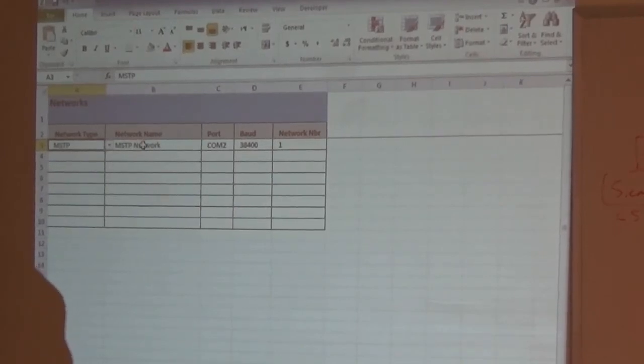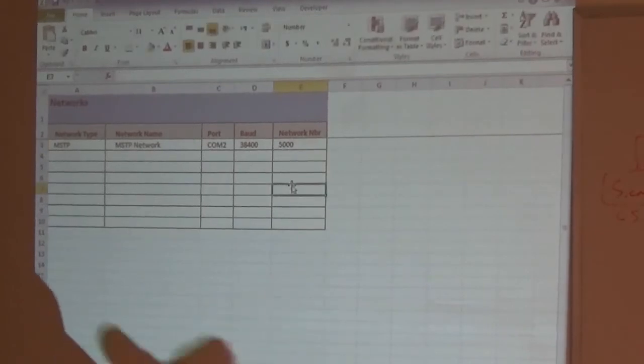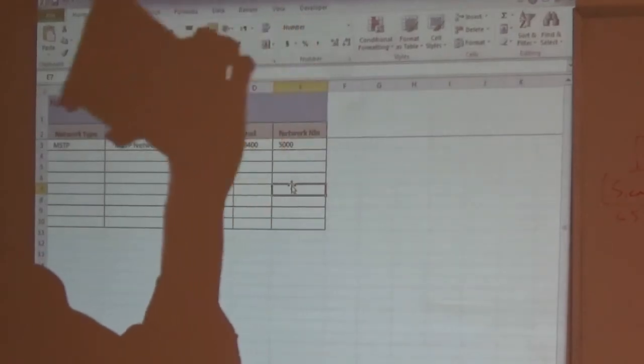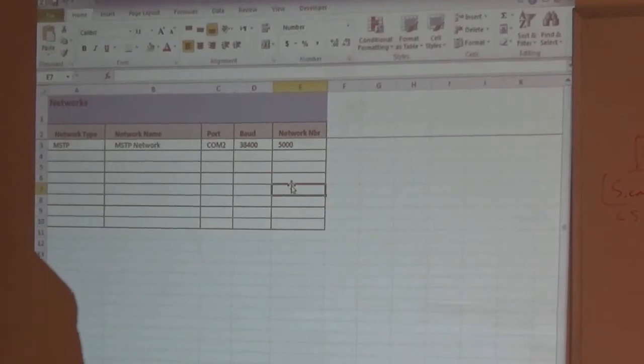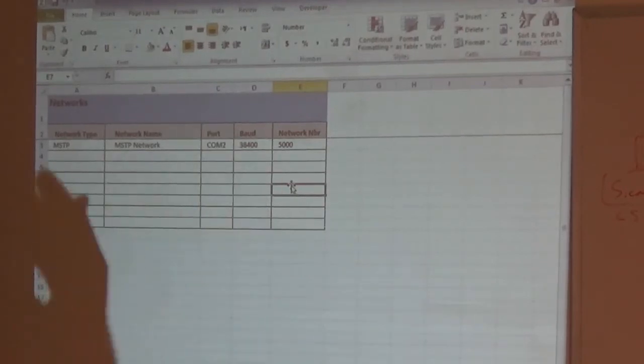It fills in the network name, free to change if you want, automatically picks the right COM port - the first one, COM2 - automatically picks the right baud rate, and it's up to you to give it a network number, like 5,000 or whatever you name your networks. You want separate network numbers across the board, since you could have up to 5 networks here, and you don't want any duplicates across the BACnet network. So 5,000 - that's what I use - and then as I add my controllers, I give them 5,000 plus whatever the MAC address or MSTP address is, so they all have separate BACnet object IDs.